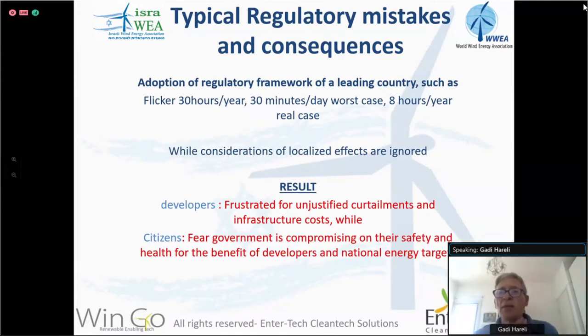If you exceed that specific amount of hours per year or minutes per day, you have to assure you do not exceed 8 hours per year in the real case. To clarify, when you have to account for the real case, you have to introduce technologies that ensure there's no flicker beyond that amount, at least here, which also translates to extra expenses, curtailment, and so on.